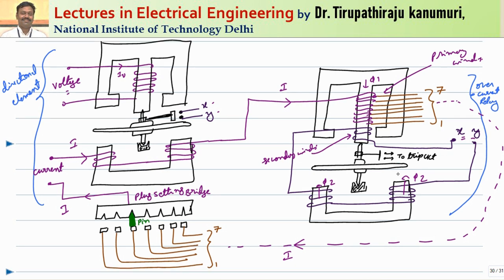The interaction of flux phi 2 and the primary flux phi 1 produces torque in the disk of the overcurrent relay. Whenever the current crosses the pickup value, the disk starts rotating and closes the trip circuit. The key point is: if the power is not flowing in the intended direction, the directional relay disk will not rotate, so contacts x and y remain open, keeping the secondary winding open-circuited. With phi 2 equal to zero, no torque is produced in the overcurrent relay even if current exceeds the current setting. The x-y contacts close only when the directional relay disk rotates, thereby adding the directionality feature.